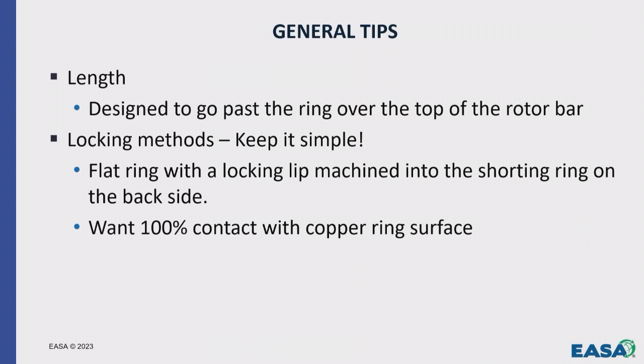So whenever you want to install new shorting stainless steel rings, whether you're replacing old ones or we're doing a conversion, we go for about at least 95% coverage on the shorting ring OD, and then we always extend it past the brazed joint from the bars to rings itself, because what that does, like I said before, is give you a double pin support joint for the rotor bar, adds good support for the braze, and also if anything was to ever break, it would trap the bar in there.